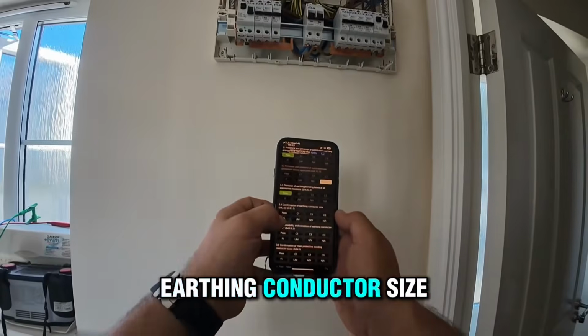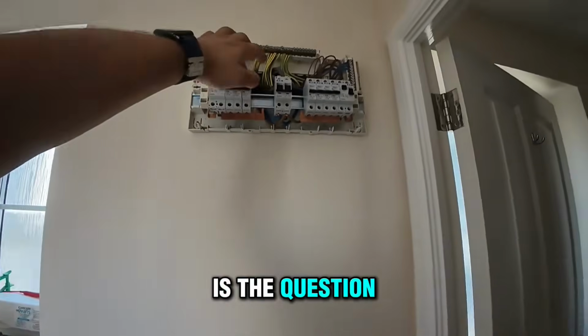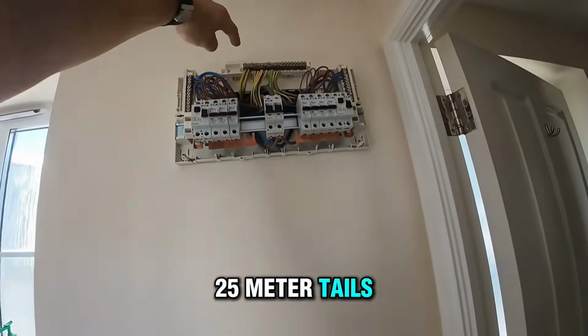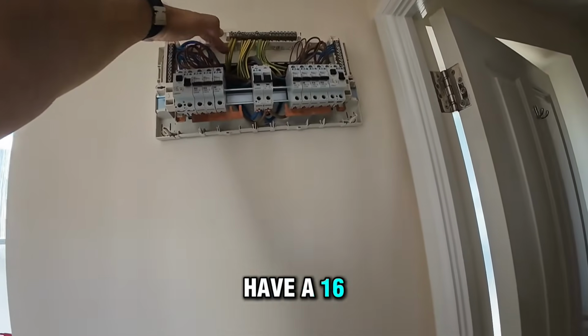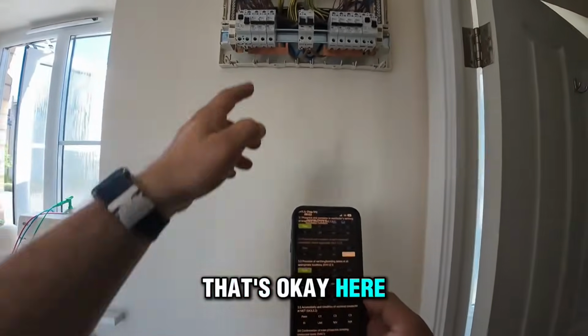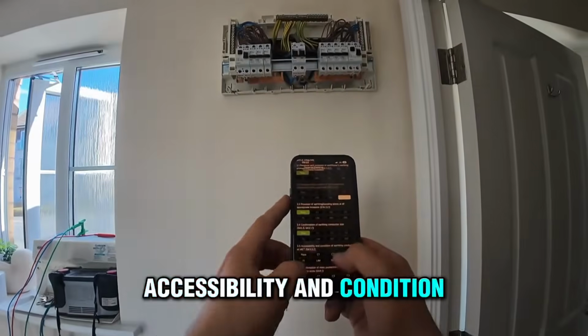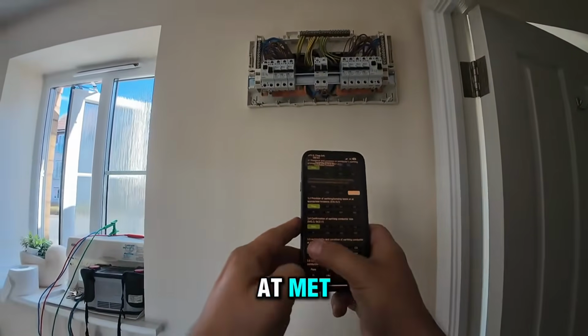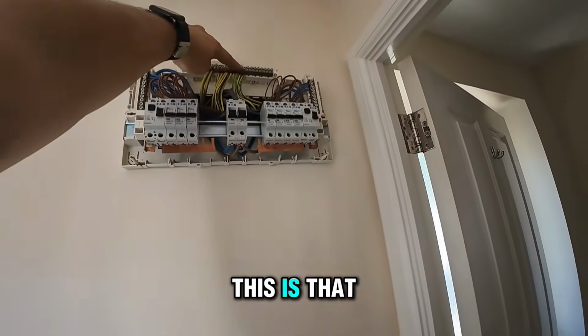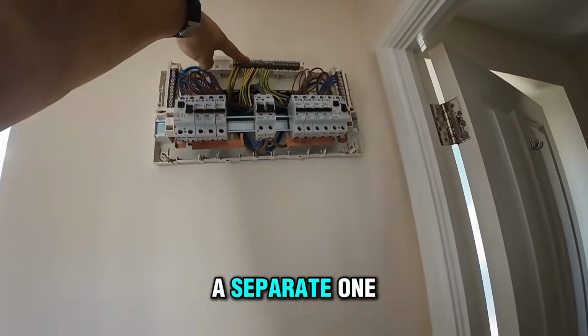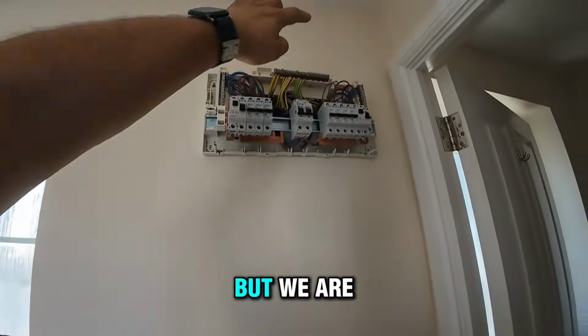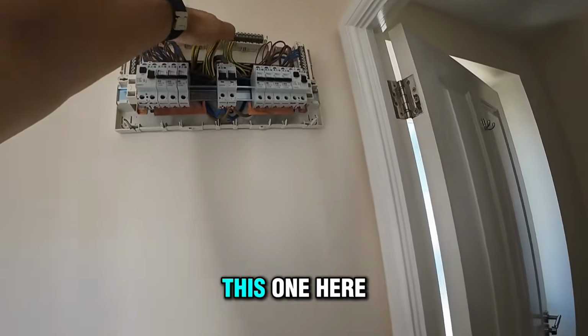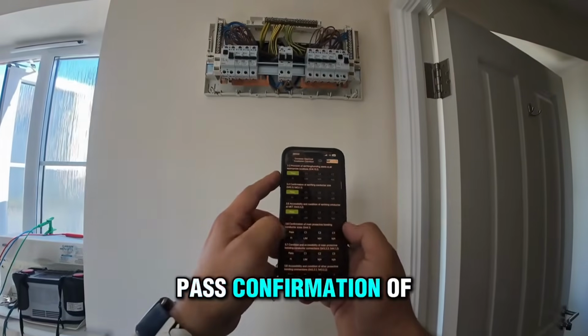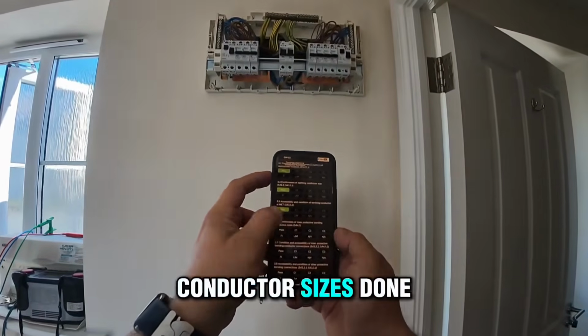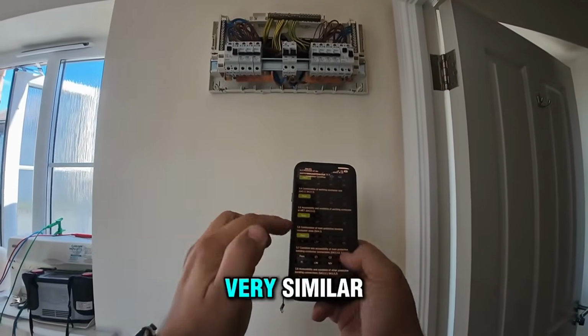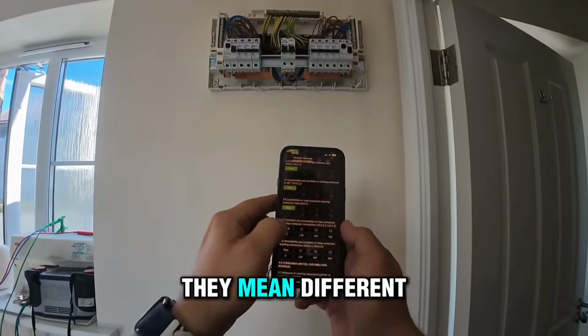Confirmation of earthing conductor size, yes. So this is the question: if you've got 25 millimetre tails, you have to have a 16 millimetre earth, and that's okay here. So is the bonding. Accessibility and condition of earthing conductor at the MET, main earth terminal. This is that bad boy. Sometimes there is a separate one outside the fuse board, but we are just relating to this one here. Pass. Confirmation of main protective bonding conductor sizes, done. So you see the questions are very similar, but they are different questions. They mean different things.